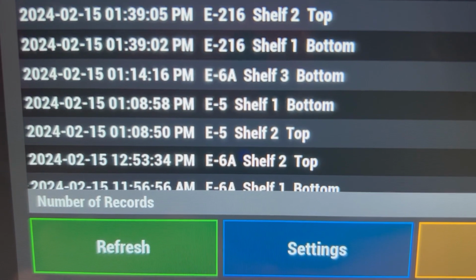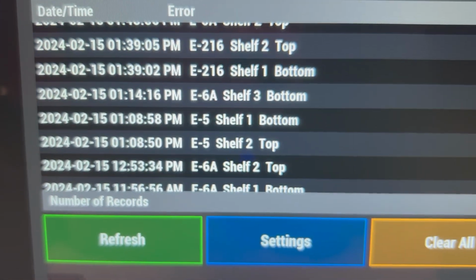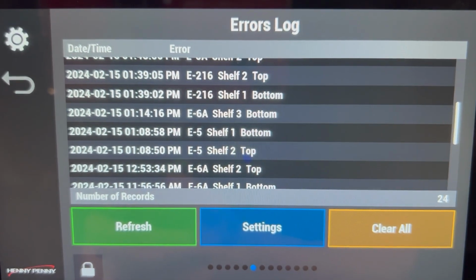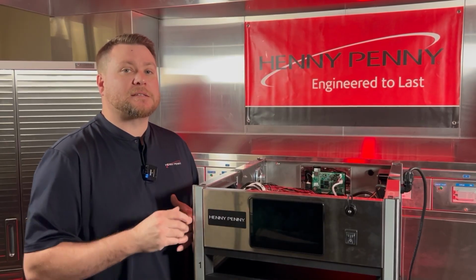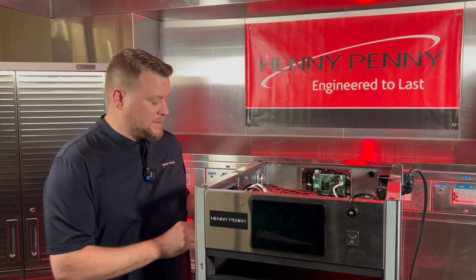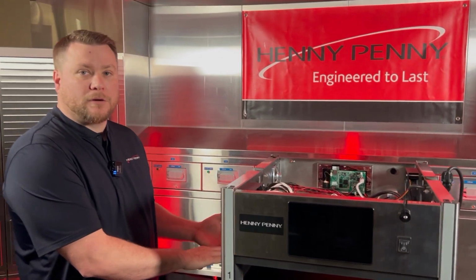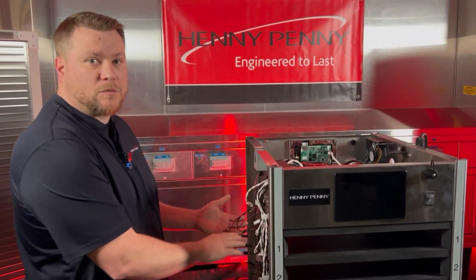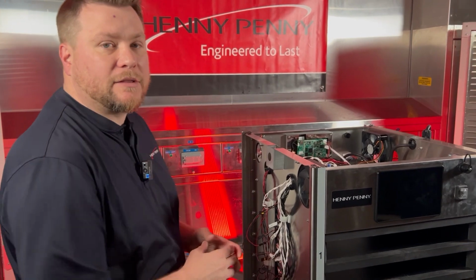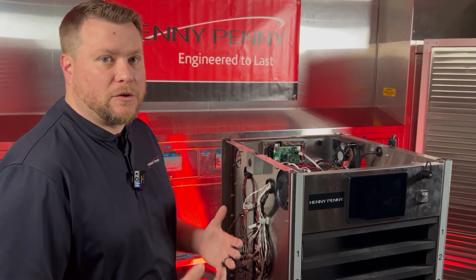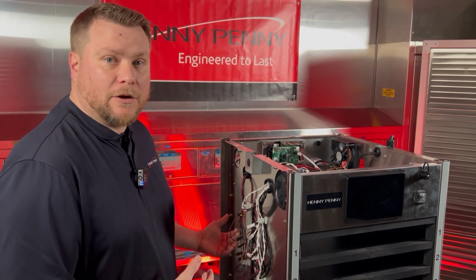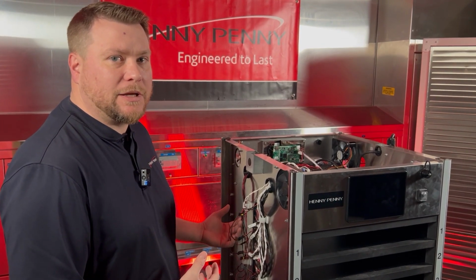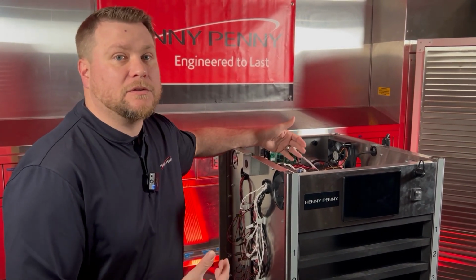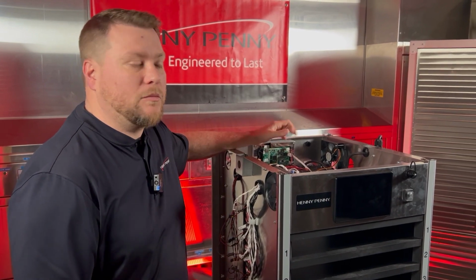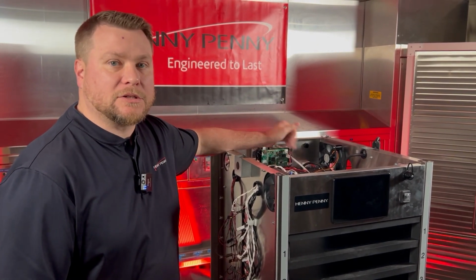Remember, on the error logs, it's going to tell us exactly which probe that was, whether it was a heat sink probe, whether it was heater number 3 versus heater number 9, etc. It's going to tell us that. So what we can do is unplug our temperature probe over here on the side. If it is one of our heater probes, we can plug that back in just to make sure that it wasn't a faulty connection.